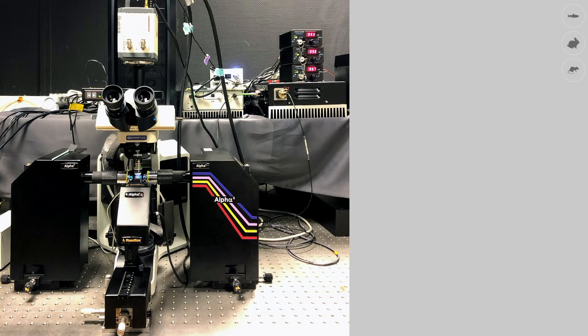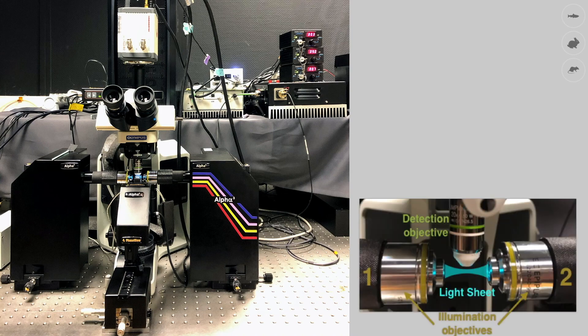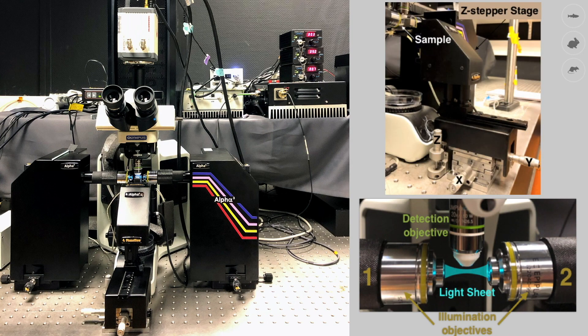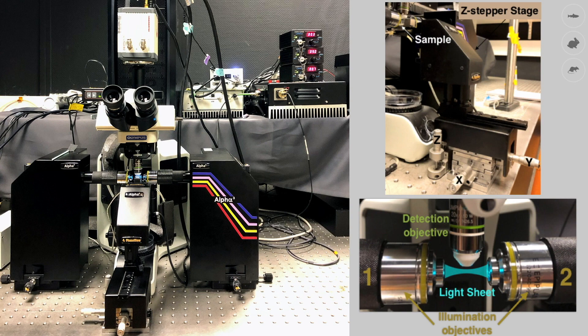This is one type of light sheet microscope available in an imaging facility. The main components of this microscope are two illumination objectives and one objective for detection, a stage for xy positioning and z sectioning, lasers to illuminate the sample with four different wavelengths, and an ultrafast and sensitive camera for signal detection.